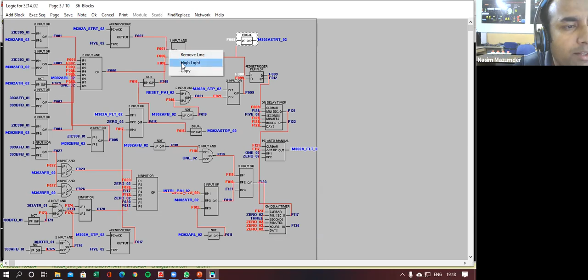Suppose I have understood that this is the particular command that will start my motor, M302A start. Now, since there is an equal sign, that means if this particular F008 becomes high, then the motor will be started. When will F008 become high? I am going in reverse order. When this AND gate gives an output of 1, that happens if all 3 pins, input 1, input 2, and input 3, are 1.